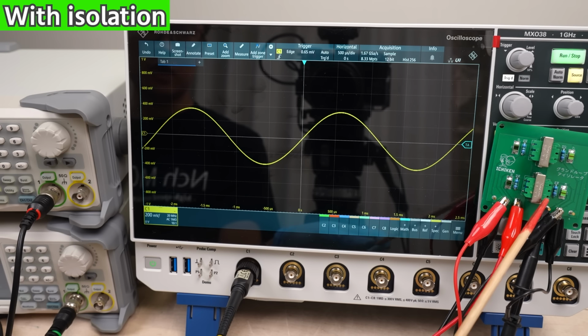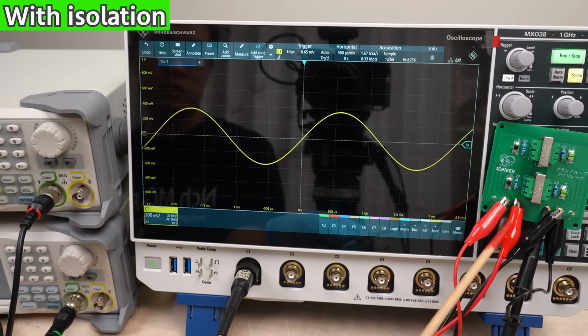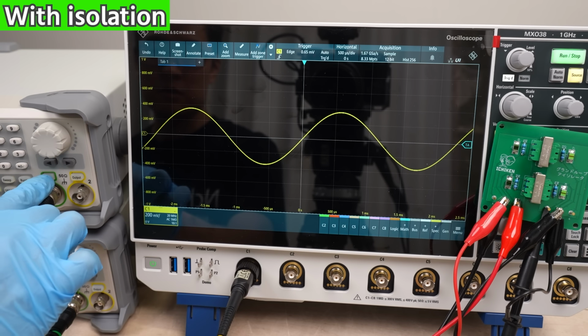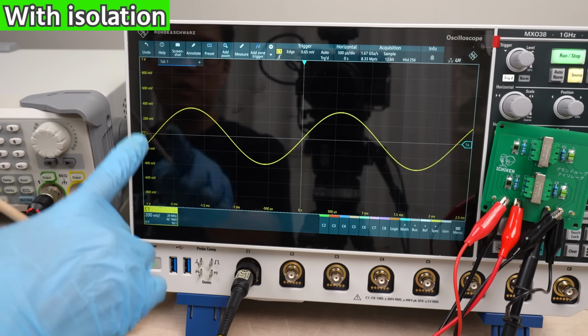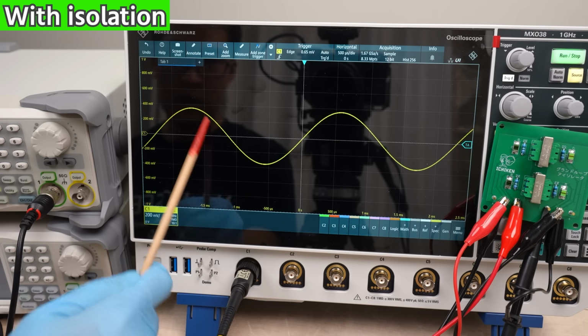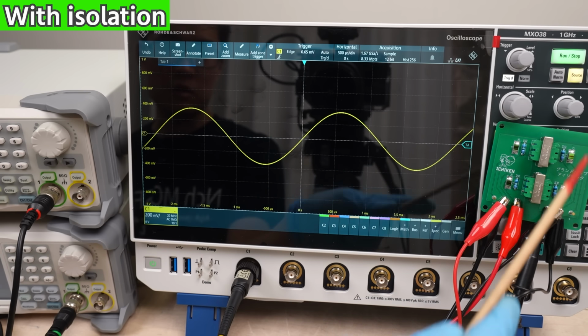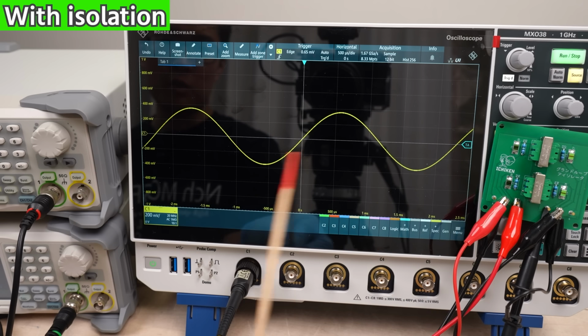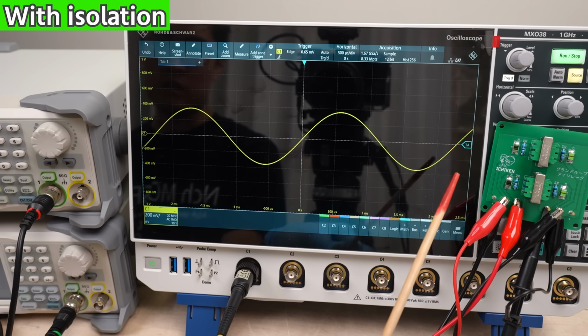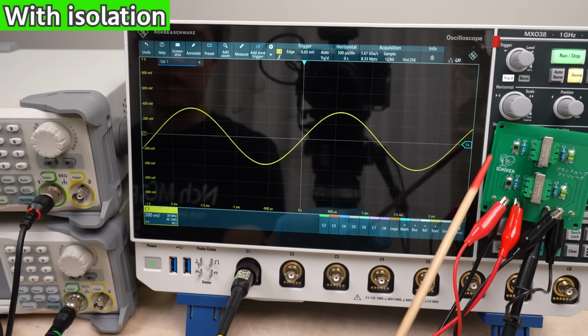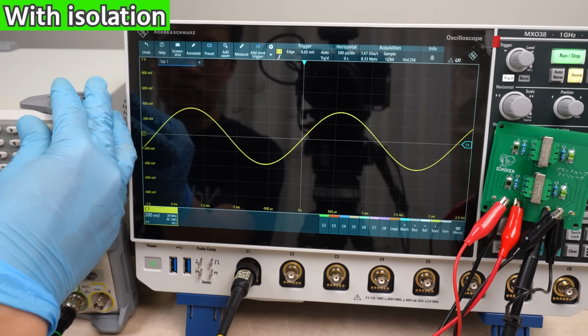Next, let's look at the case with a ground loop isolator. We'll inject ground loop noise. So, what happens? There is almost no effect at all. The waveform remains unchanged. This is the power of the ground loop isolator. However, the isolator cannot eliminate every type of noise. Let's see what happens when high-frequency ground loop noise is introduced.